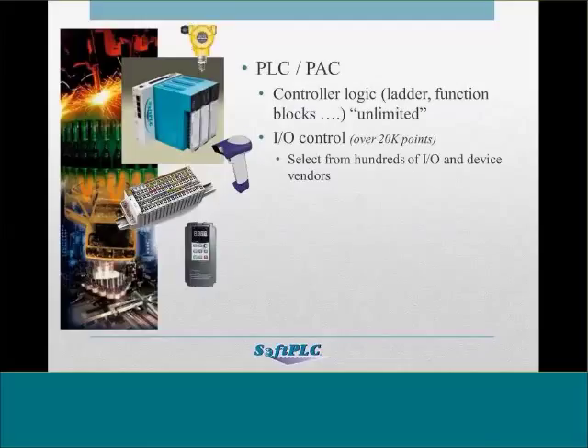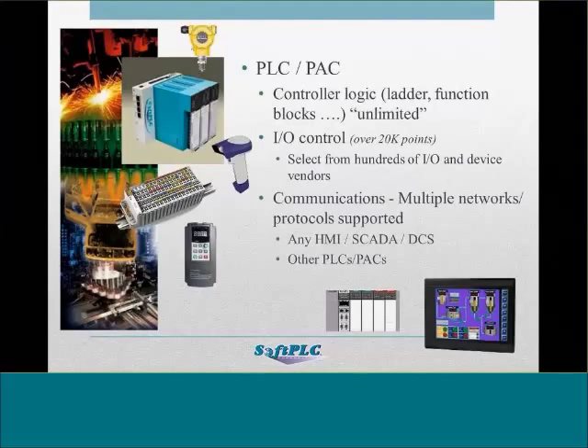You can connect to multiple different types of I/O simultaneously. And since it's open architecture, we can talk to devices from hundreds and hundreds of vendors. As far as communication goes, you can configure the PLC to support multiple networks, connecting to any HMI, SCADA, or DCS system via standard protocols like Modbus, Modbus TCP, DF1, other Ethernet protocols, Profibus, and so on. We also can talk peer-to-peer to other PLCs, so if you've got Modbus devices, Allen Bradley PLCs, or other SoftPLCs, they can send messages back and forth.